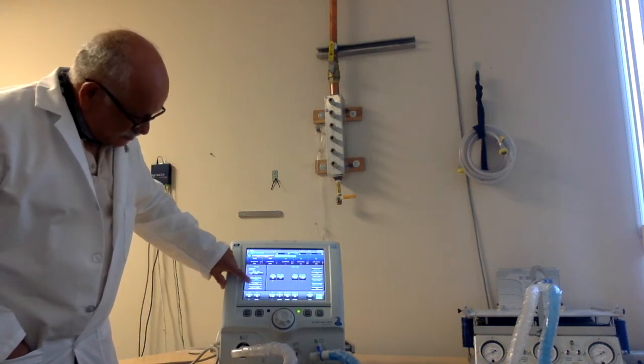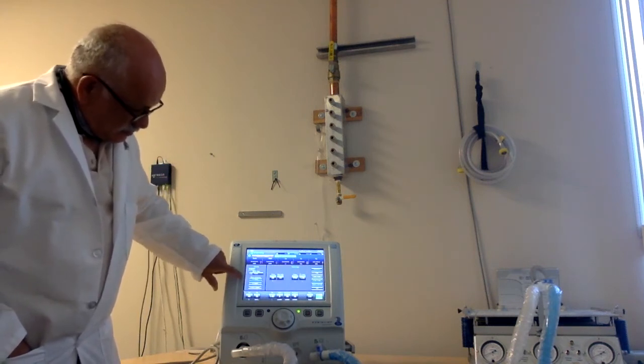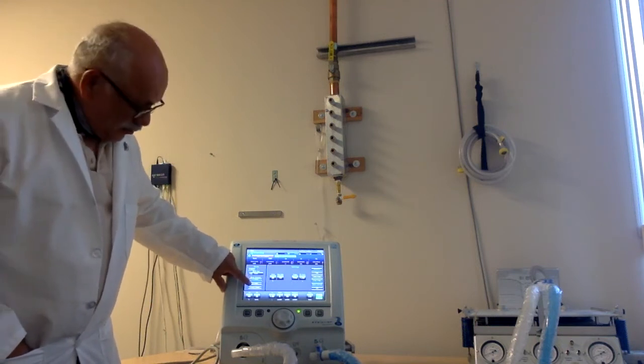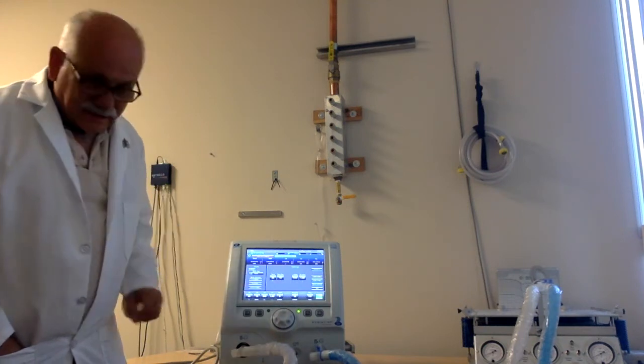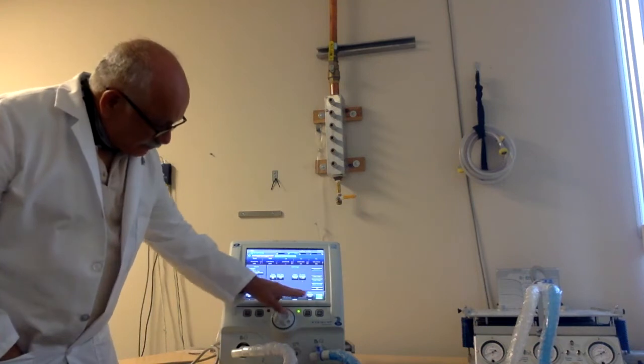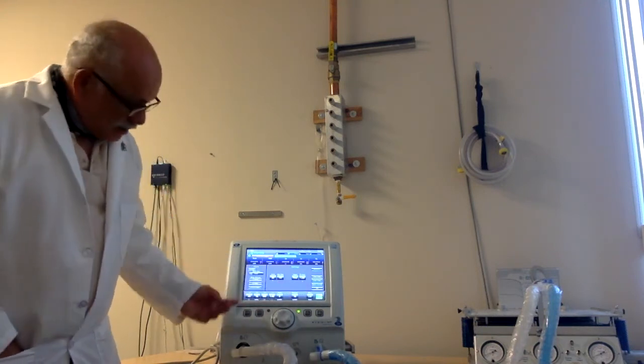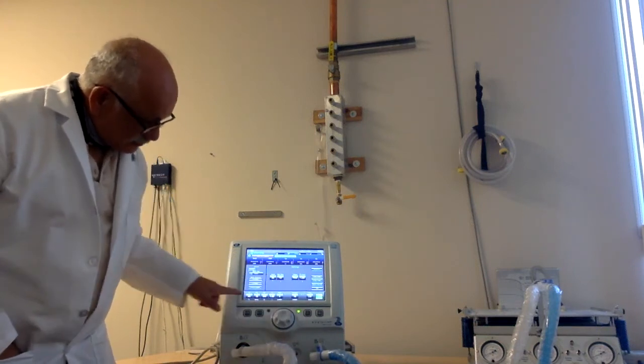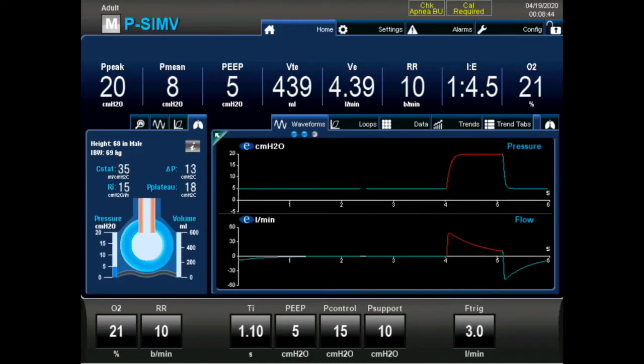Notice that as I change the types of SIMV, whether it's volume or pressure, or PRVC, yet another very important mode we'll cover, the pertinent parameters along the bottom are presented. Again, take a look along the bottom section. In this ventilator, very similar to other ICU-quality ventilators, you'll find patient monitoring above, digital monitoring. You'll find the pertinent parameters along the base. Pertinent parameters are parameters that you need to change often, or that are very specific to the mode type of ventilation, or to the breath type and mode type of ventilation. And then you'll have waveforms across the screen. We'll talk about waveforms later.